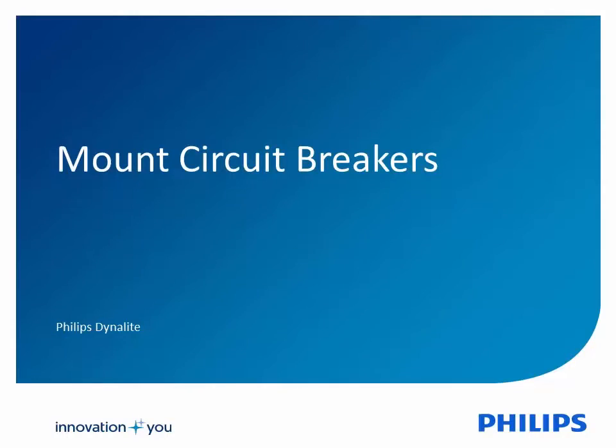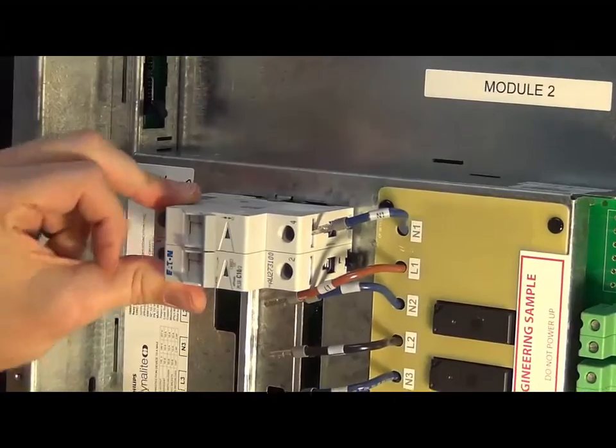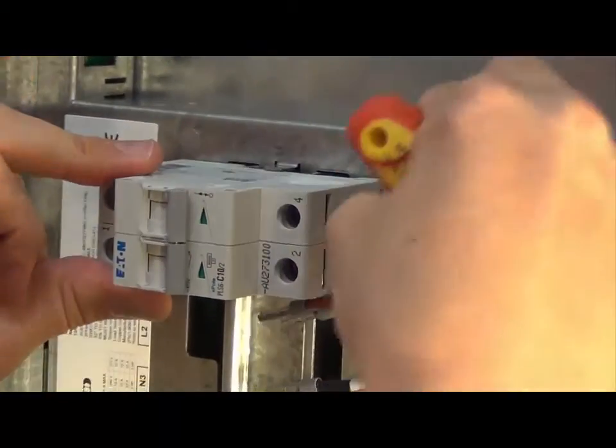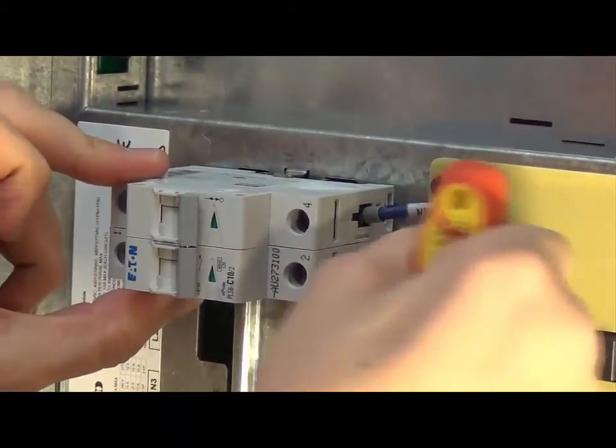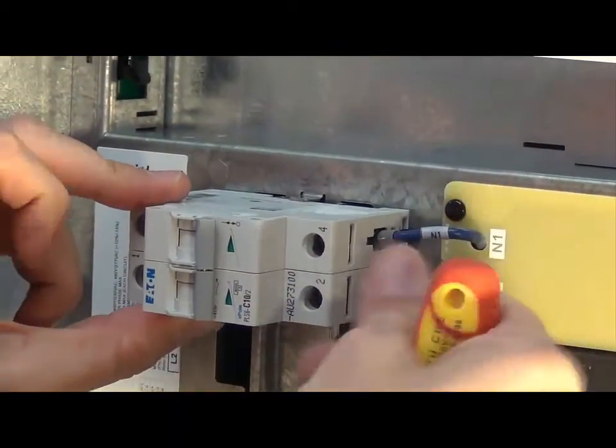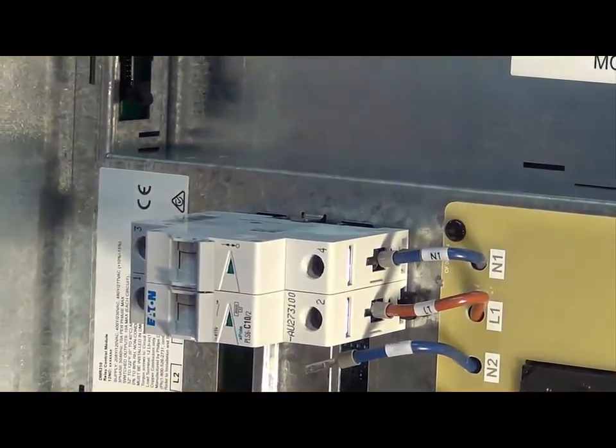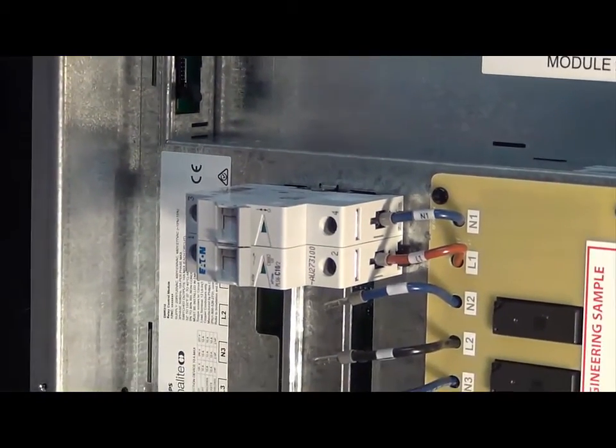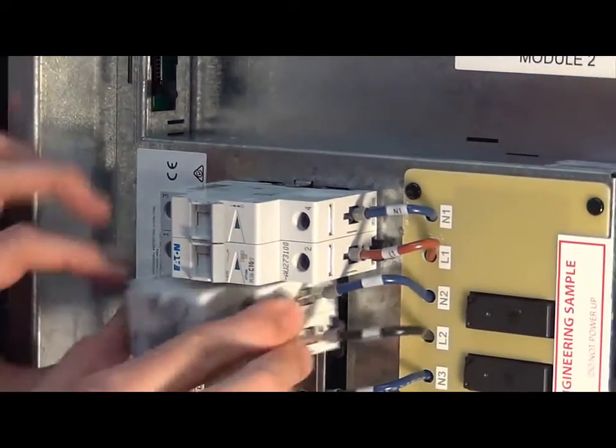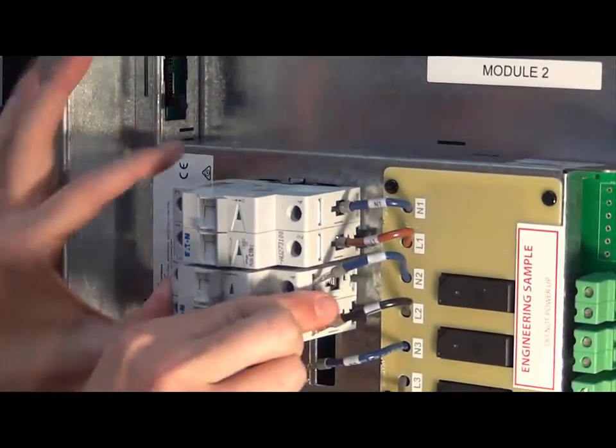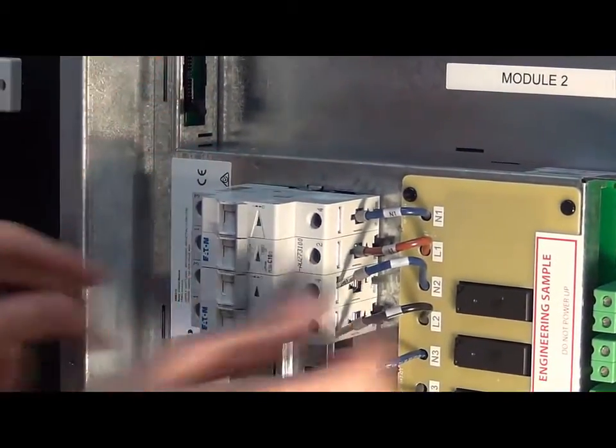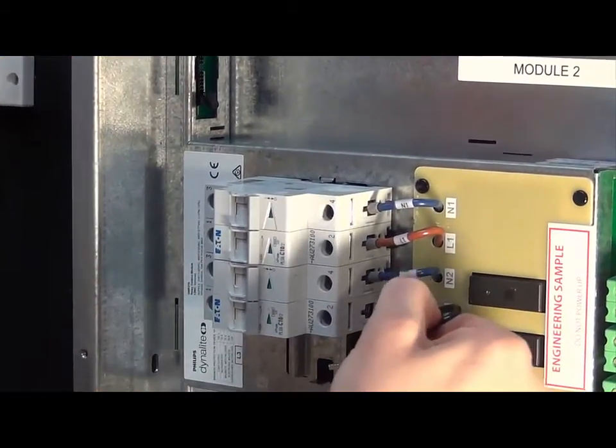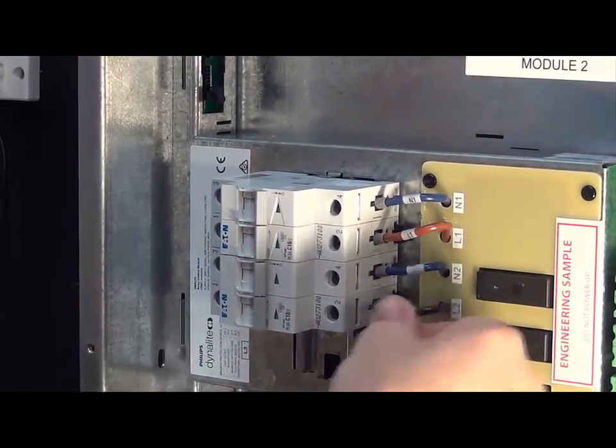Mount the circuit breakers. Use only the circuit breakers provided in the installation kit. Mount them so that they are isolated when switched towards the output side. Terminate the output wires from the control module into the right side of the circuit breakers.